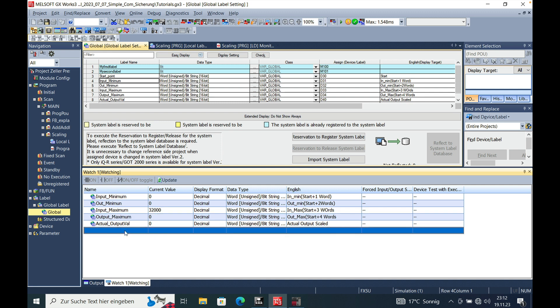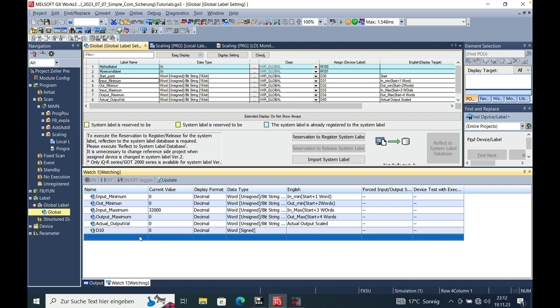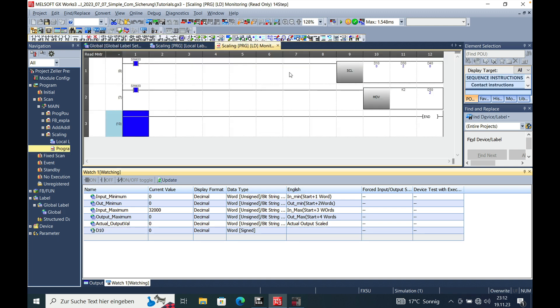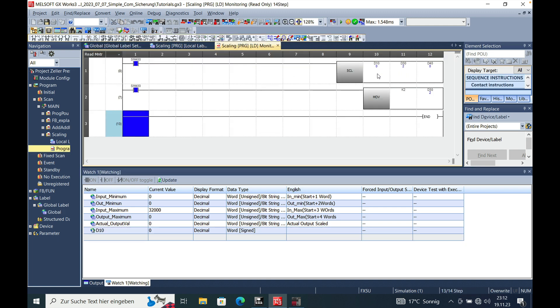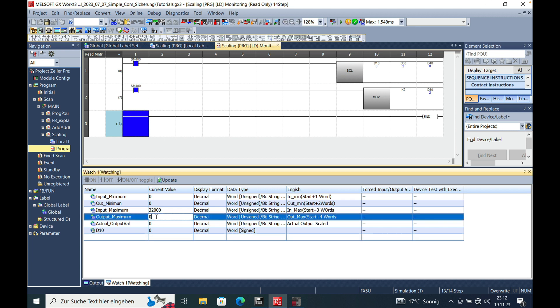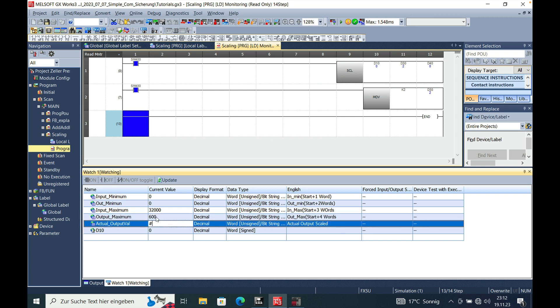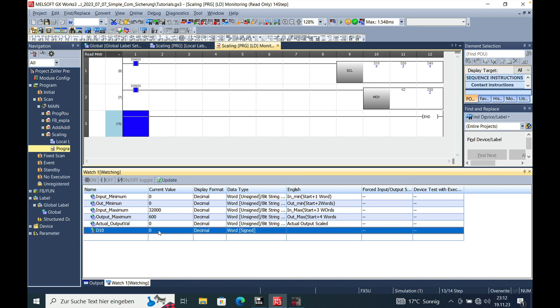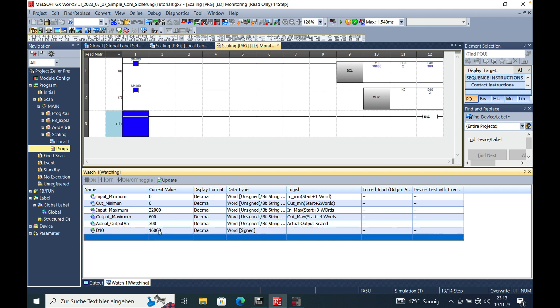And then we also need the input value from our D10 that I just put in here. This is actually moved from the FX5 input to the D10. So our output should be the 600 mm. And then we will see, let's say we have a value of 16,000. That should bring us to an actual output value of 300 mm. And there you go.